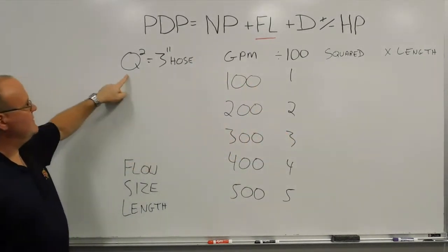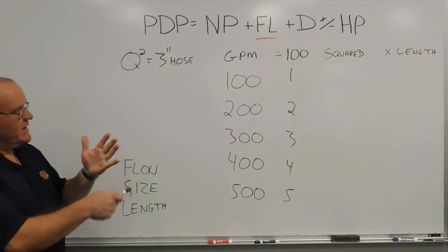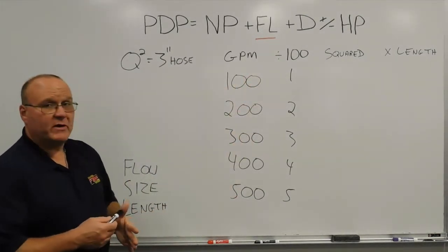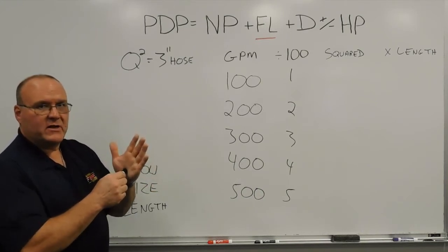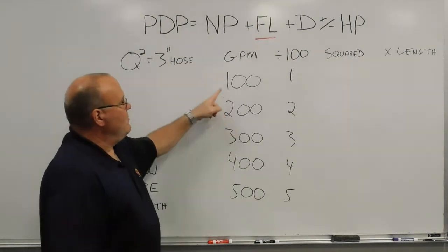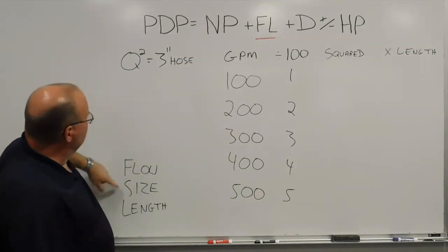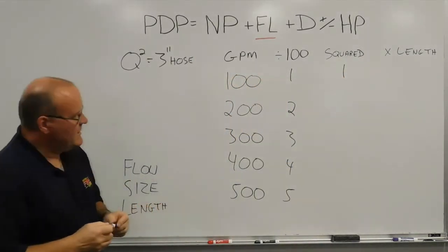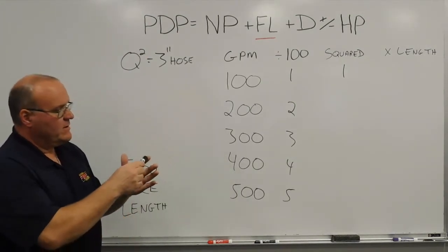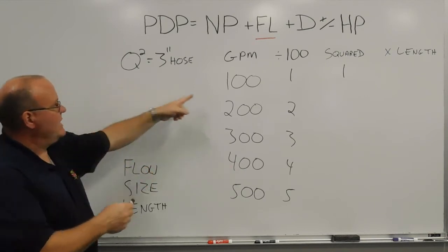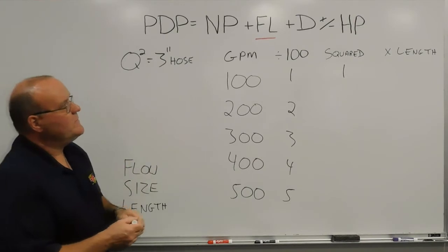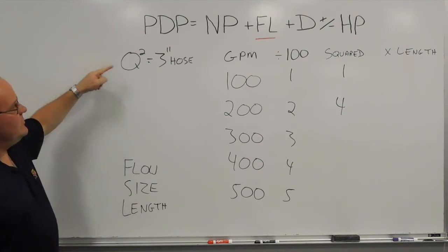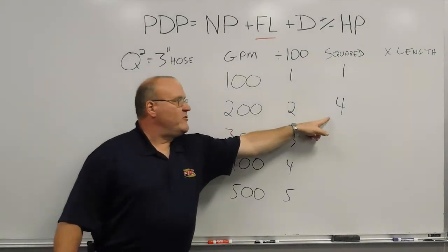From that number, go right to your Q-squared — this is where your hand calculator comes in. For 100 gallons a minute: divide by 100, get 1. There's our multiplication sign — we square it: 1 times 1. So for every 100 feet of 3-inch hose flowing 100 gallons a minute, there's 1 pound of friction loss. For 200 gallons a minute: divide by 100 gives 2, then 2 times 2 gives 4. So for every 100 feet of 3-inch hose flowing 200 gallons a minute, there's approximately 4 pounds of friction loss.